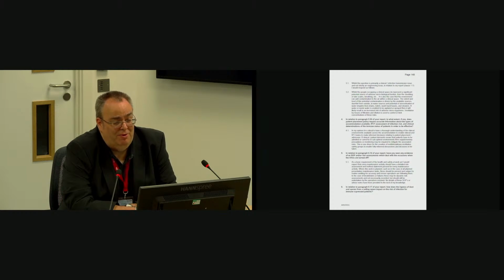You must have an understanding and awareness of the ventilation as one element, and as I say, I concentrate primarily on ventilation, but it needs to have enough electrical socket outlets. They need to be emergency generator backed up if necessary. There's a whole myriad of stuff. You can't just say, I have a patient, I have a room, therefore I can put that patient into that room. It needs to be done in coordination and knowledge of what the room is, how it performs, what services are present, and what that patient is likely to need.